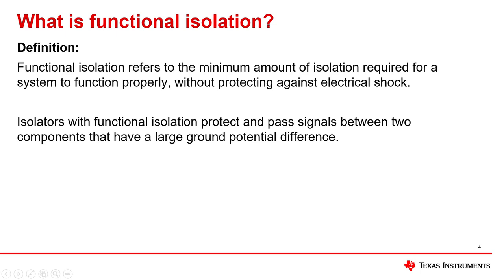So what is functional isolation? Functional isolation is the minimum isolation required for a system to function properly. Unlike basic or reinforced isolation, functional isolation does not intend to protect from electrical shock. Instead, it protects signals from high ground potential differences to prevent signal inaccuracies.